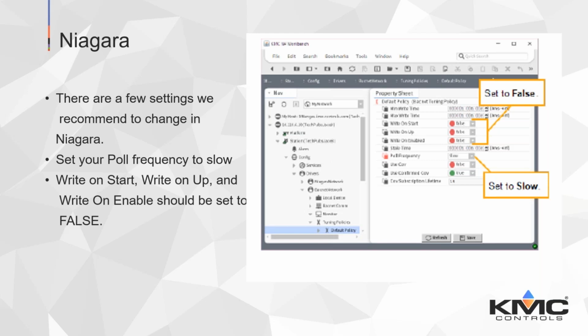And you can change the time on that. You can change the time on that. So if your points are going stale, then it's probably an indication that you need to add more time to the token cycle. If you've got some points going stale or possibly going orange, that means Niagara didn't hear back from them quick enough. So you might change that speed. Okay. Slow it down a little bit more. We're trying to merge 20-year-old technology and technology from today, so it's a little slow.